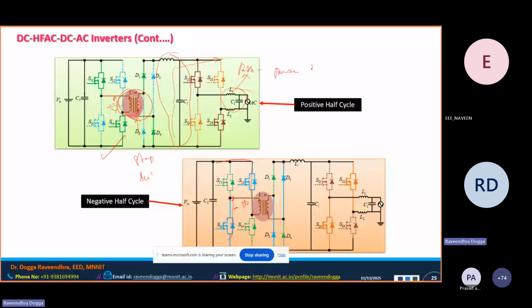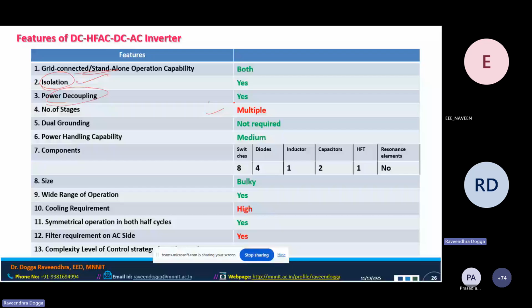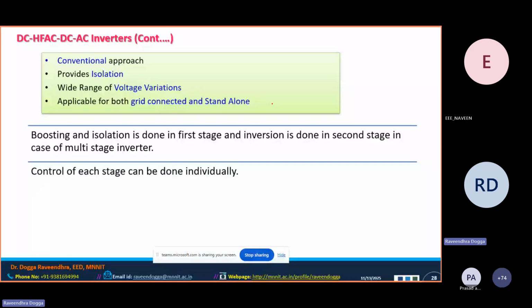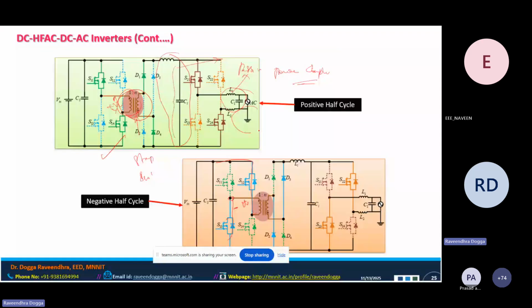Number of stages are multiple, more than 3, and dual grounding is not required because you are already having a very good isolation. You don't even need to connect your PV module to the ground because you are having isolation. It is not required.